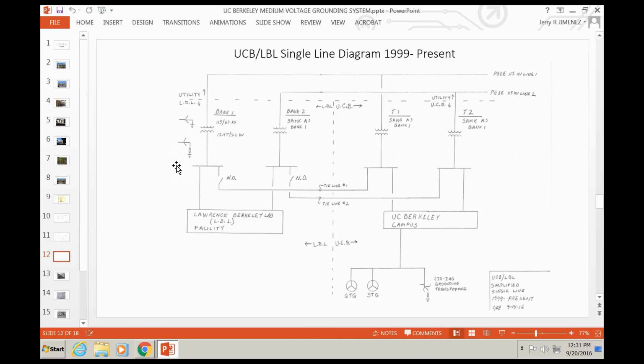However, being affiliated with the system for the last 17 years, I'm very much in favor of the 1,000 amp value. 3,000 amps, I don't think you need 3,000 amps. I think 1,000 amps does everything you need it to do, and it minimizes the damage in comparison with a 3,000 amp grounding resistor. Of course, you're not getting that everywhere. What's your longest feeder, and what kind of cable are you using?